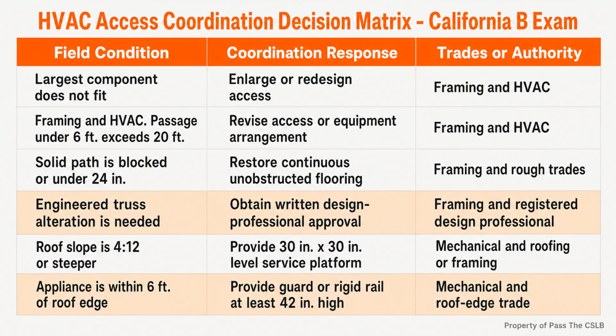Roof-mounted appliances add slope and edge conditions. When an appliance requiring service is on a roof with a slope of 4 units vertical and 12 units horizontal, or 33%, or greater, a level platform at least 30 inches by 30 inches is required at the service side.